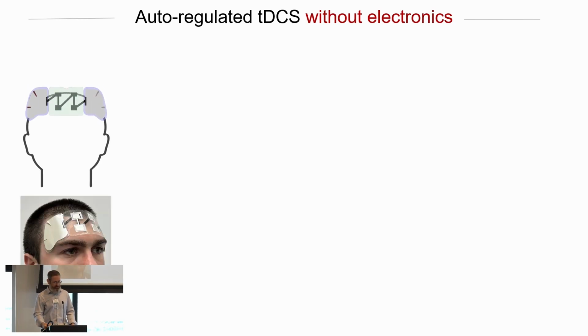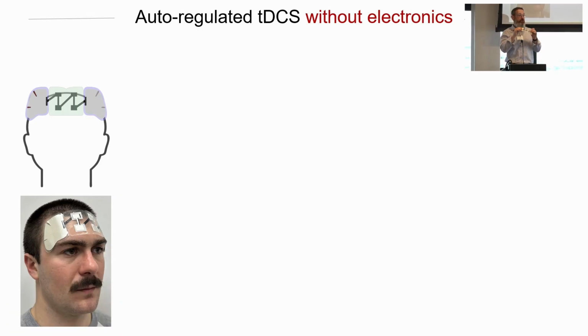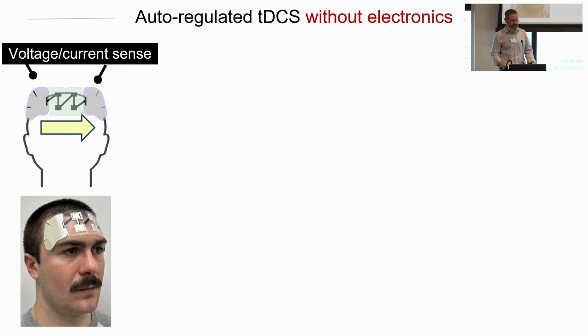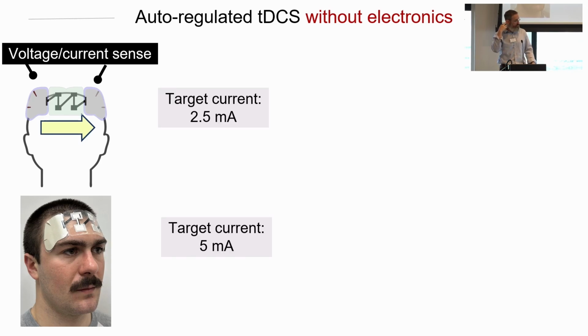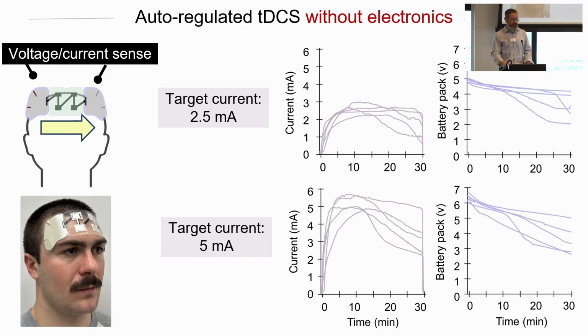This is what the device looks like on the head. As soon as it's placed, it starts to discharge. Now, how do we know that it's doing what it's supposed to do? Well, there's no electronics in here to give us that information, so we just need to have little tabs, and we add a source meter on top of it. So that's how we are able to validate that it's doing what it's supposed to do. I mentioned we have 2 target currents that we're interested in. And a long story short is, across multiple subjects, the devices were doing what they were prescribed to do. They were ramping up, hitting a target current, and then ramping down.